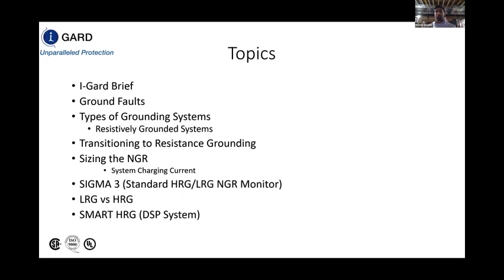We'll also be discussing types of grounding systems, including a more in-depth focus on resistively grounded systems and how we can transition to a resistance grounded system, depending on if we're solidly grounded or ungrounded. In addition to that, I'll go over the sizing of the NGR, what factors are important that we need to consider, and I'll also be discussing our standard HRG offering as well as our smart HRG offering, as well as what code and standards requirements are indicating for high resistance grounding.